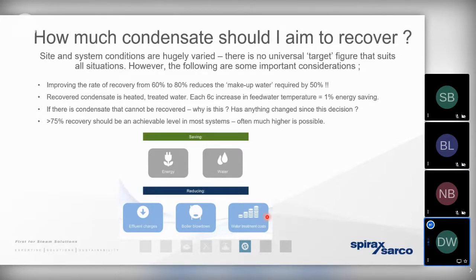It's impossible to expect that we should be recovering 100% because, as we've already mentioned, some of those processes could be using steam for direct injection purposes, at which point there is no condensate to recover. And as we mentioned in the previous presentation, it's inevitable that we may have the occasional leaking steam trap. We may have the occasional flash steam vent, both of which mean that we're losing steam to atmosphere, and therefore that condensate isn't available to be returned.